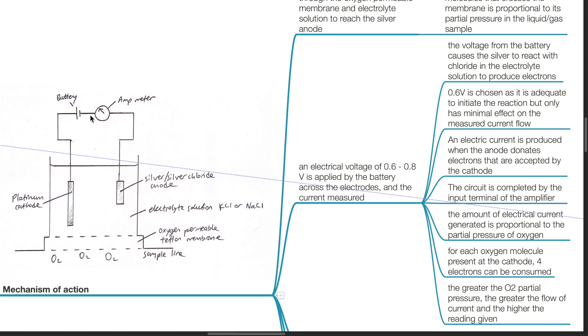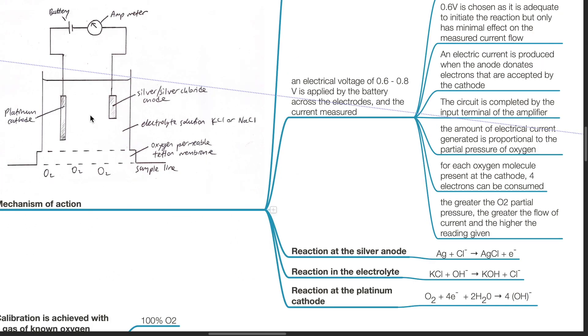An electric current is produced when the anode donates electrons that are accepted by the cathode. The circuit is completed by the input terminal of the amplifier. The amount of electrical current generated is proportional to the partial pressure of oxygen. For each oxygen molecule present at the cathode, four electrons can be consumed. The greater the oxygen partial pressure, the greater the flow of current and the greater the reading given.